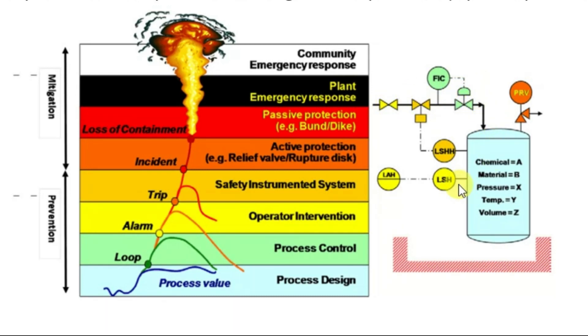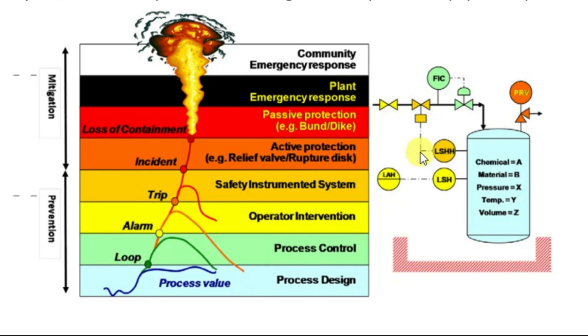There are level switches for high-level indication and another level switch for high-high indication, based on which the emergency block valve will shut. The tank level keeps on increasing and cannot be controlled by the control valve function. When it reaches the level switch high-high limit, the sensor will sense and give a signal to close this emergency block valve. This is the operation sequence.